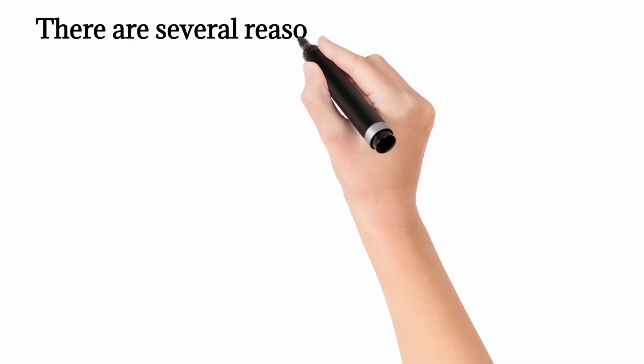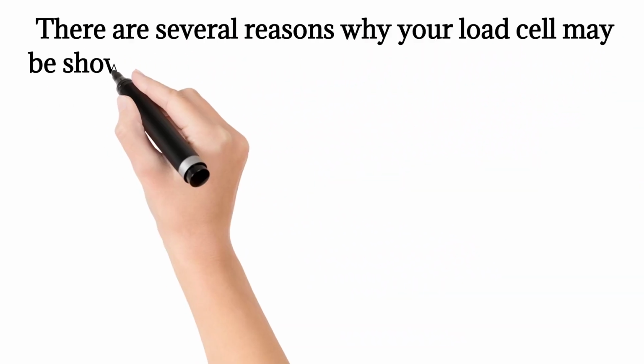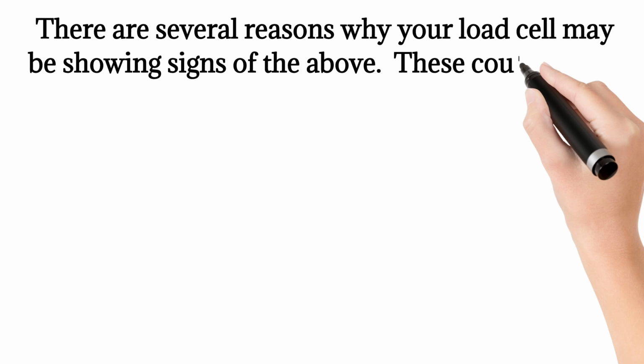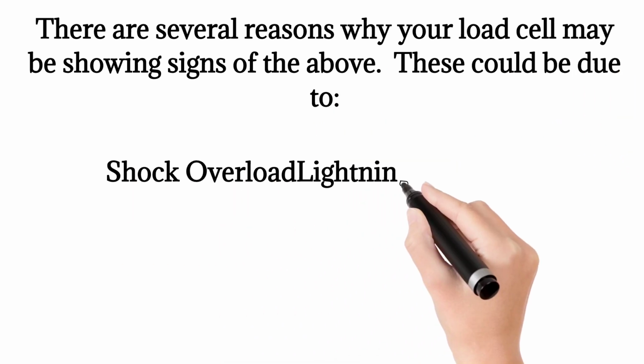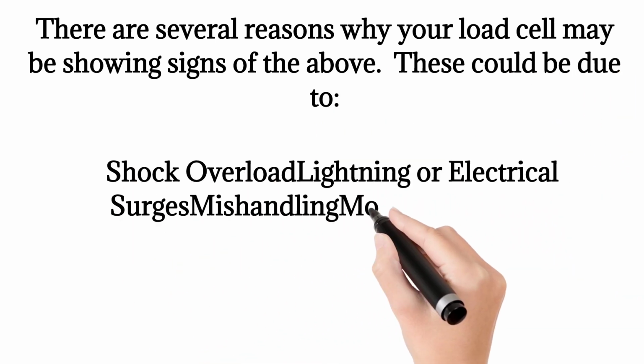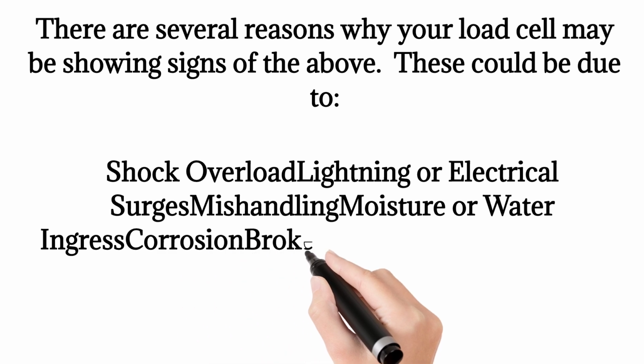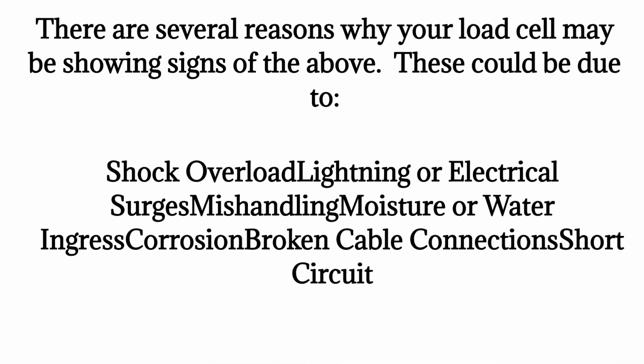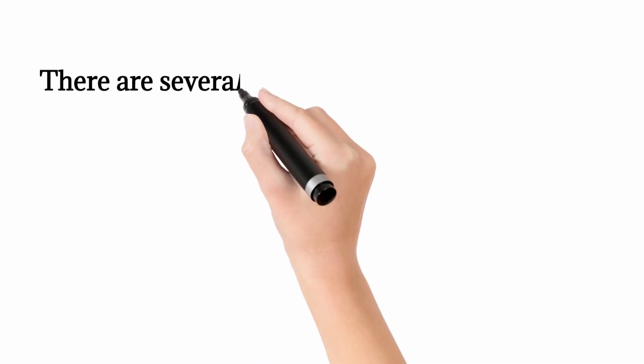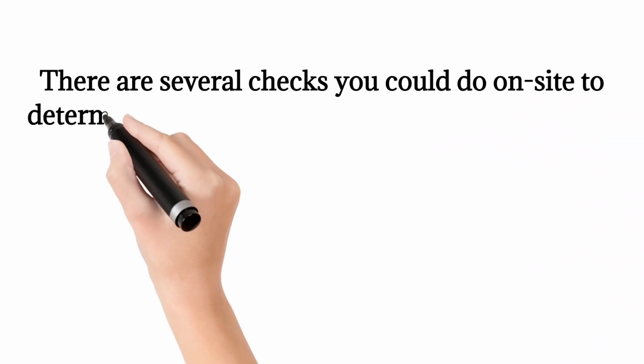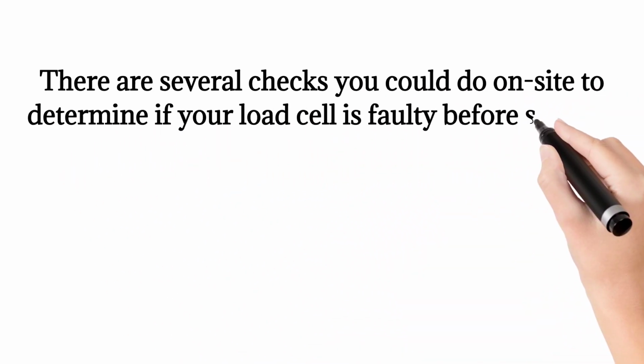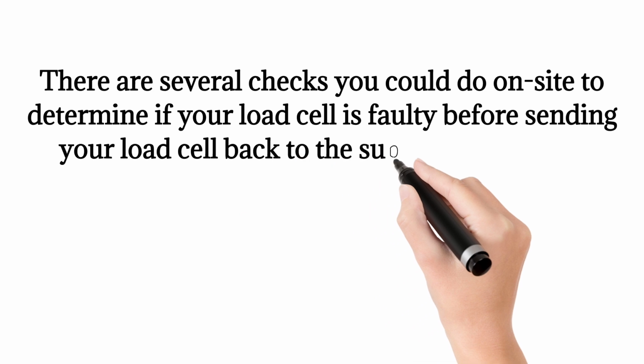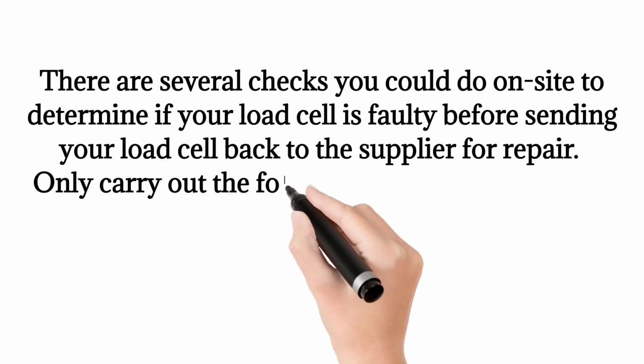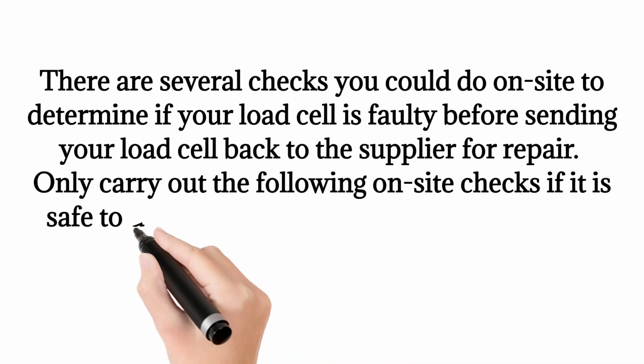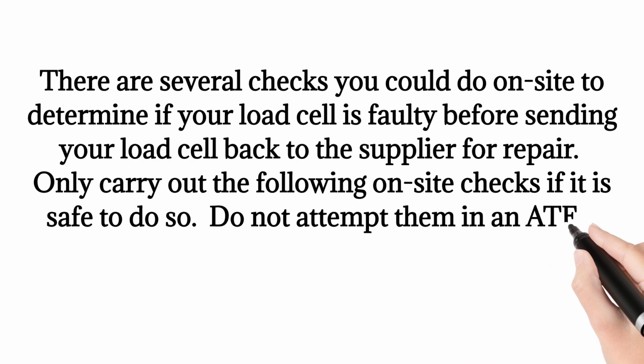There are several reasons why your load cell may be showing signs of the above. These could be due to shock overload, lightning or electrical surges, mishandling, moisture or water ingress, corrosion, broken cable connections, short circuit. There are several checks you could do on site to determine if your load cell is faulty before sending your load cell back to the supplier for repair. Only carry out the following on-site checks if it is safe to do so. Do not attempt them in an ATEX hazardous area.